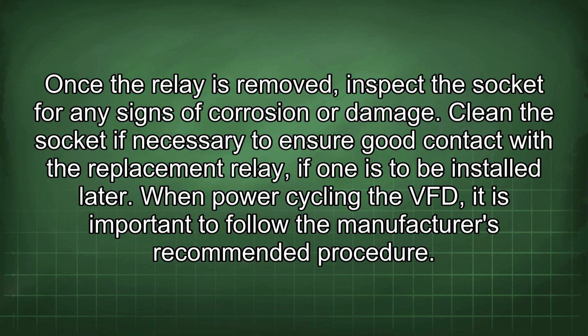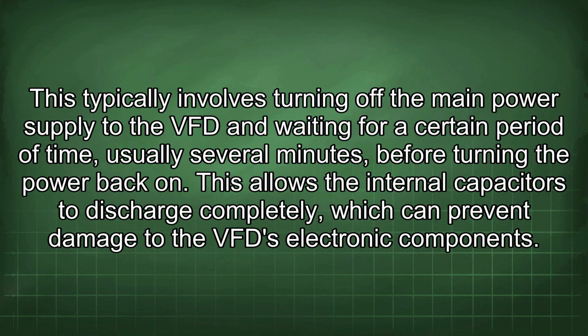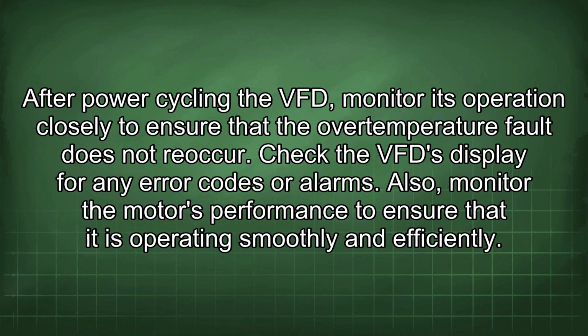When power cycling the VFD, it is important to follow the manufacturer's recommended procedure. This typically involves turning off the main power supply to the VFD and waiting for a certain period of time, usually several minutes, before turning the power back on. This allows the internal capacitors to discharge completely, which can prevent damage to the VFD electronic components.